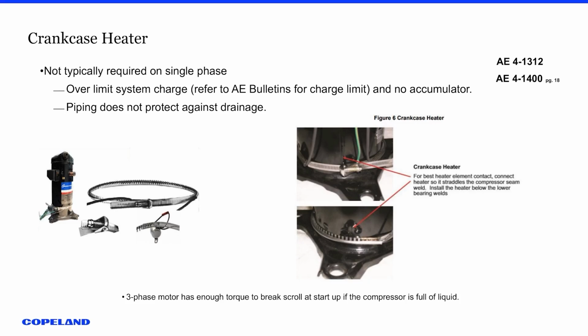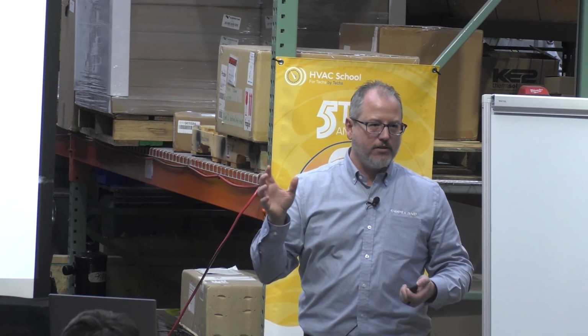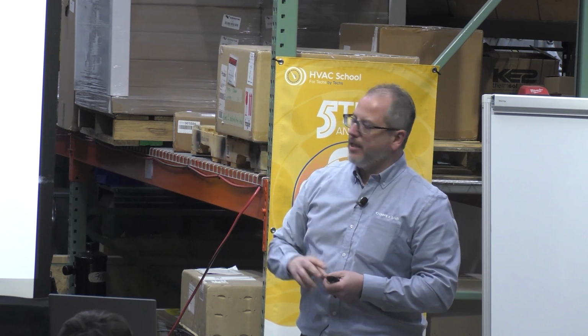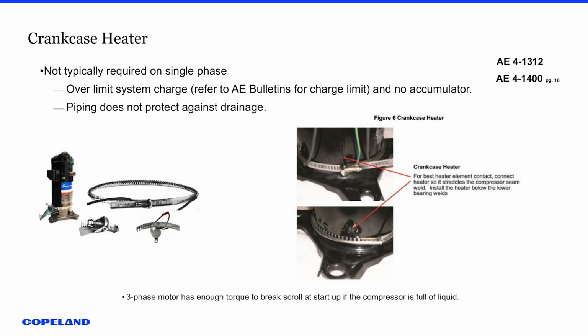With crankcase heaters, and I just threw this in there as a little added thing, we have a vertical weld in our scroll compressor, and right where they connect here, where you bolt it down to tighten it, this doesn't go real tight against the compressor. So if you put that vertical welded seam right there, it fits a lot better around that compressor, right? And if you're using our apps, you can go right to the AE bulletins, our application engineering bulletins, and it will tell you exactly what height you want to put that crankcase heater.